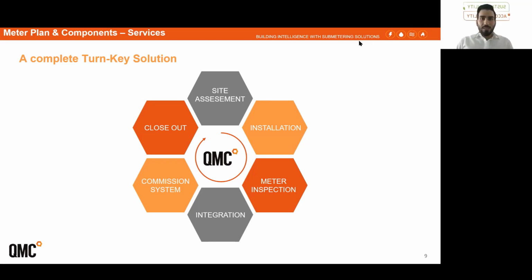Wanted to give you an example of one of my recent experiences with a commercial property downtown Toronto that we were brought into late last year to assess the steam metering that was deployed about 3 or 4 years ago on site. While we were going through the assessment, we realized we were initially called in because the total amount of steam that was being billed to the property by the district energy was not lining up with steam consumption that their sub meters were showing.